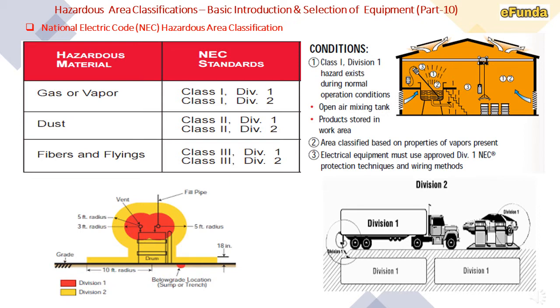NEC hazardous area classification: refer to the table where gas or vapour is Class 1 Division 1 and Class 1 Division 2; dust is Class 2 Division 1 and Class 2 Division 2; fibres and flyings are Class 3 Division 1 and Class 3 Division 2. In the petrol pump example, Division 1 and Division 2 classifications are shown — Division 1 is indicated in red and Division 2 in yellow.